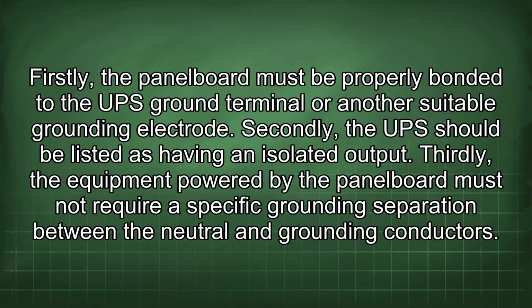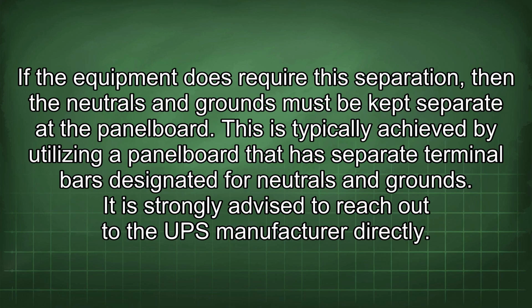Firstly, the panel board must be properly bonded to the UPS ground terminal or another suitable grounding electrode. Secondly, the UPS should be listed as having an isolated output. Thirdly, the equipment powered by the panel board must not require a specific grounding separation between the neutral and grounding conductors. If the equipment does require this separation, then the neutrals and grounds must be kept separate at the panel board. This is typically achieved by utilizing a panel board that has separate terminal bars designated for neutrals and grounds.